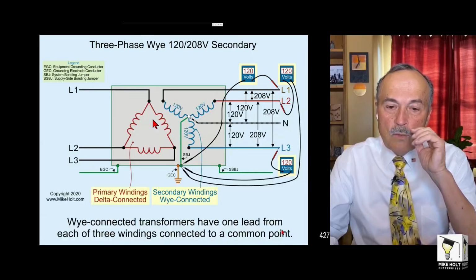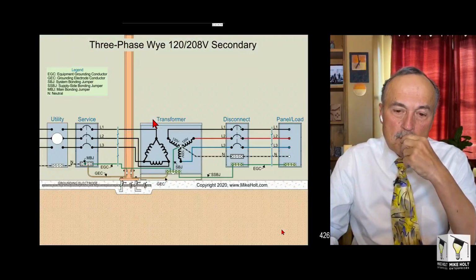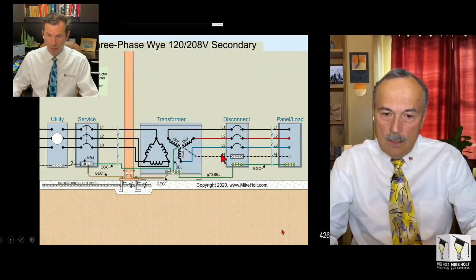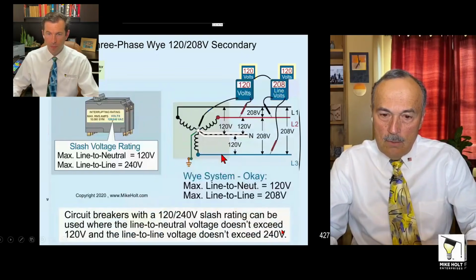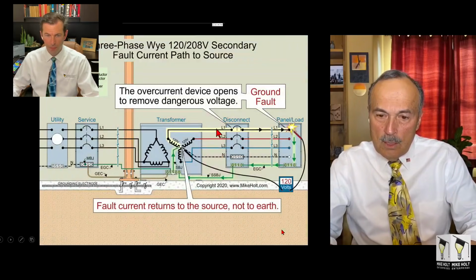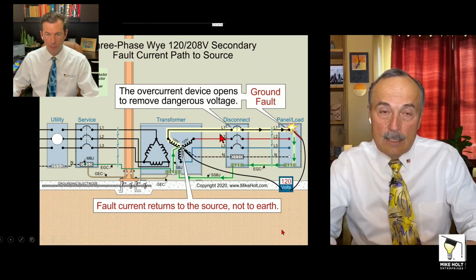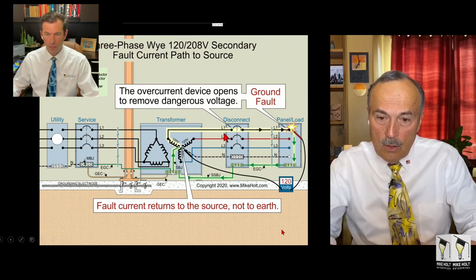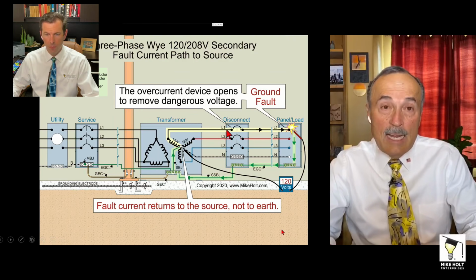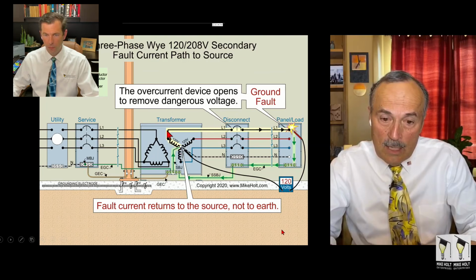All right, Brian, take one question at a time. What would happen if the ground fault occurs before the disconnect on the secondary? Let me go right here, this graphic. If this fault occurred on the line side, let's say it goes to this enclosure right here, ahead of the disconnect, then the current would leave and go to this enclosure.